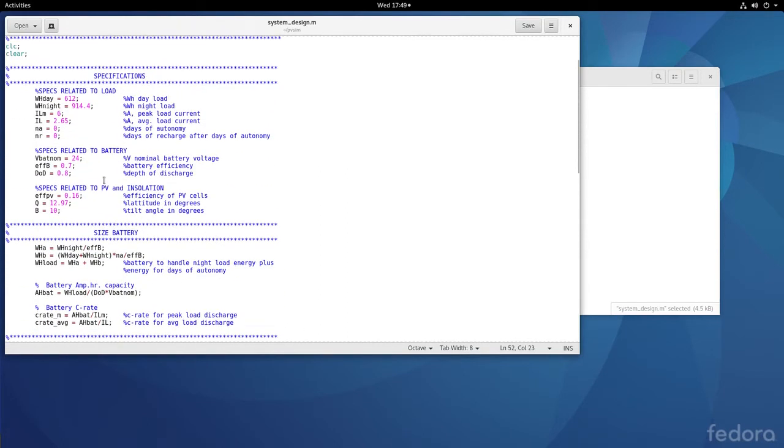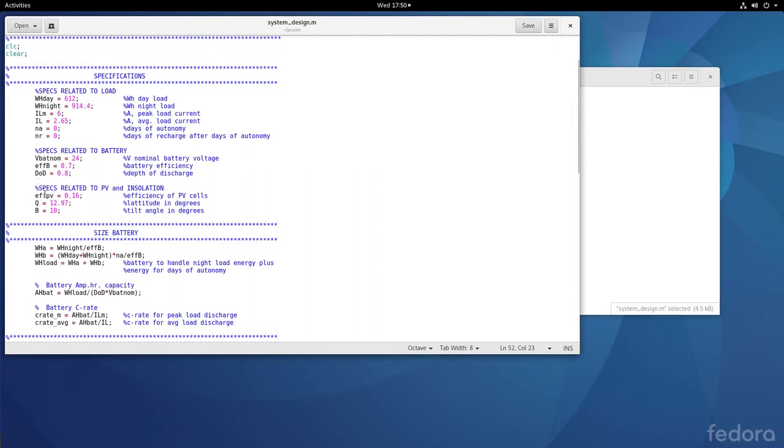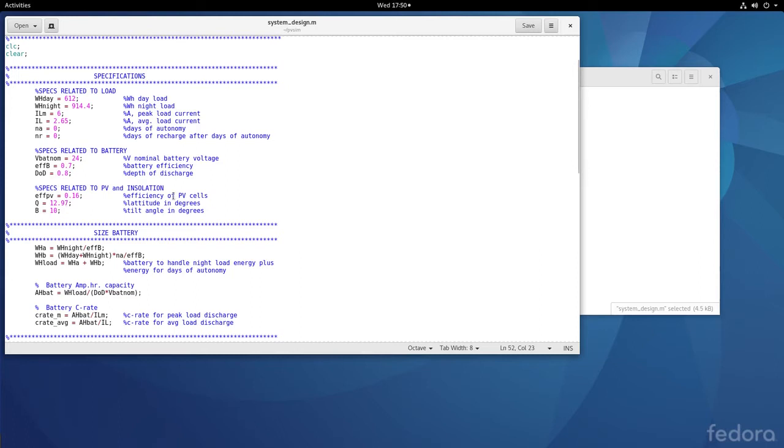I've included the same numbers we calculated by hand so you can verify them. The load specs include day and night watt-hours, peak load current, average load current, days of autonomy, and recharge days. Battery specs include nominal voltage, efficiency, and depth of discharge (DOD). PV and insolation specs include 16% efficiency, latitude 12.97° (Bangalore), and tilt angle 10°.